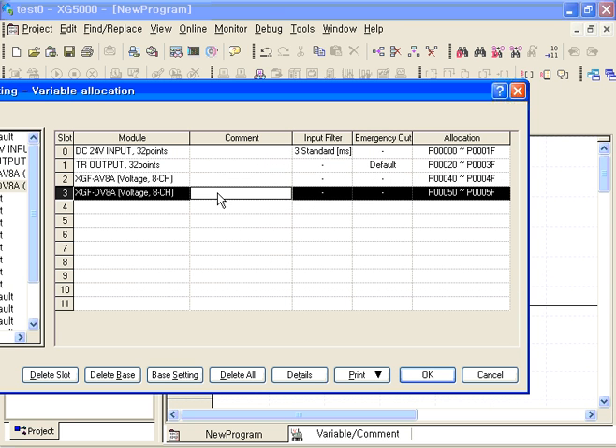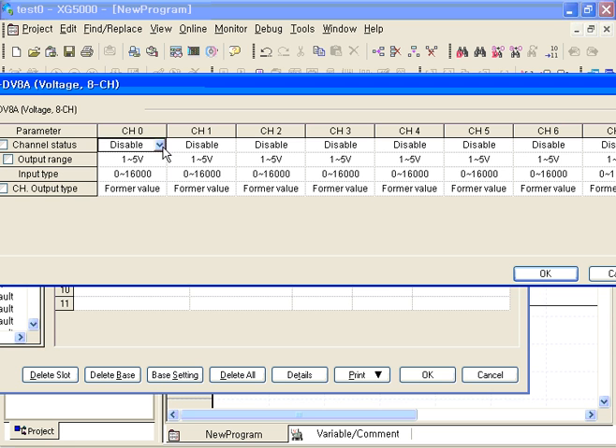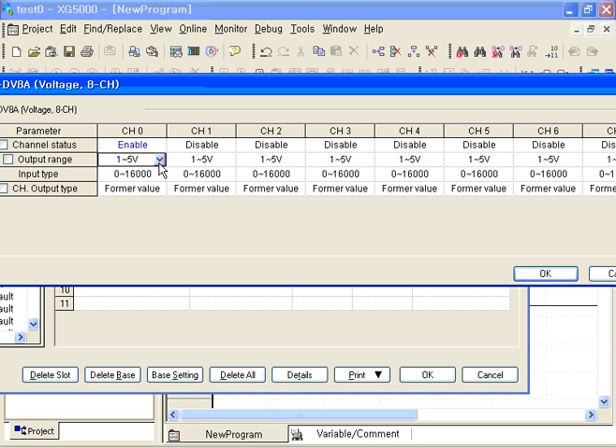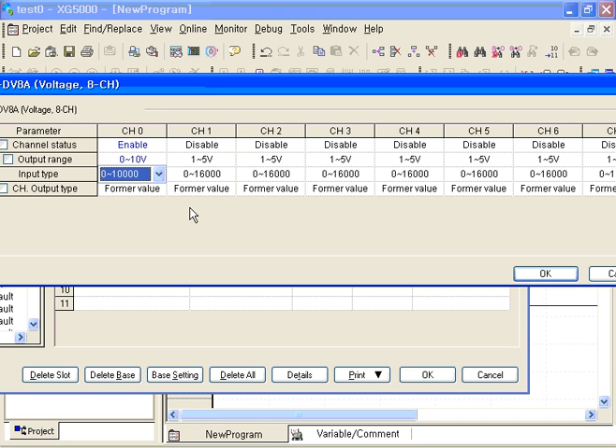And now we are going to have output. Output module the same - enable, all set the same output module like this. When you apply data value to 5000 in some special area, then this 5000 corresponding value would be made to the real output channel. So if I put 5000, then 5 volts is applied to the sensor. 6000 is 6 volts, 4 is 4. So that's analog stuff.